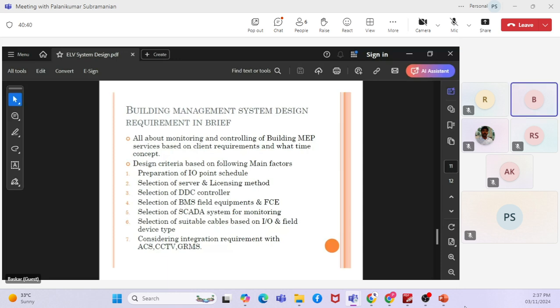And selection of suitable cables is also very important here. Why I'm saying this is, when we are choosing the cable, the thickness matters when we are using higher gauge cables for small applications, because for most of the applications we have VFC, volt-free contacts. So volt-free contacts for all the inputs where we are only monitoring. Those points come with VFC, and we can go with a minimum of 22 AWG. When we are going with field equipment and final control elements, it differs based on the type of equipment. Let's say for the actuators we need to go with 20 AWG cable, a 3-wire system, based on the control and the feedback.